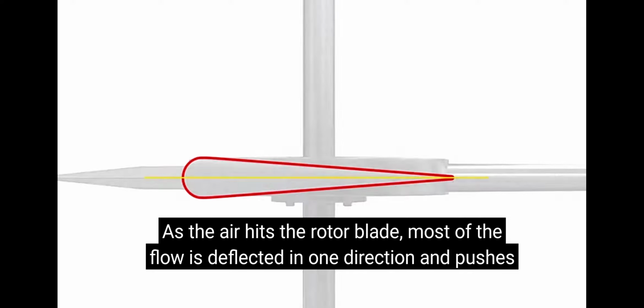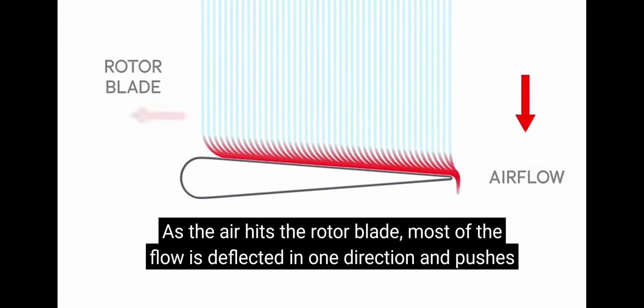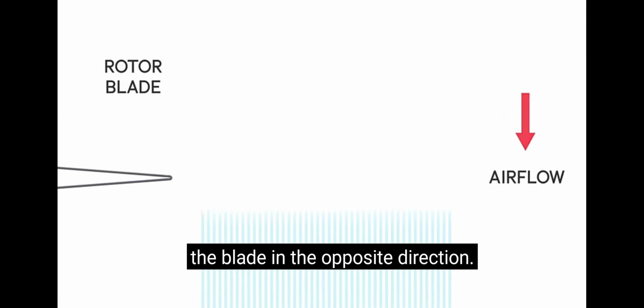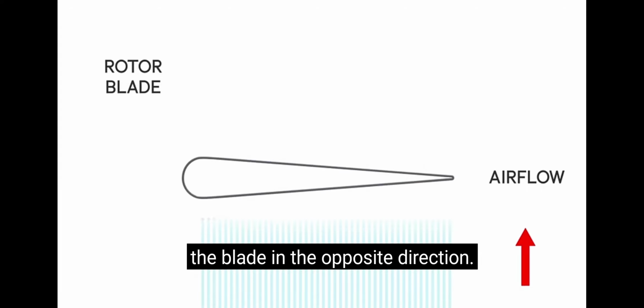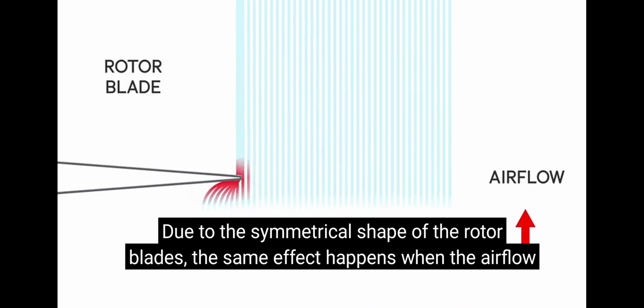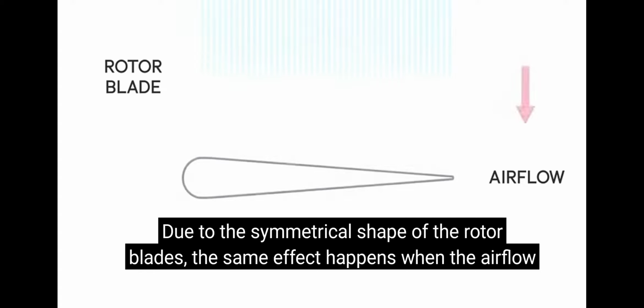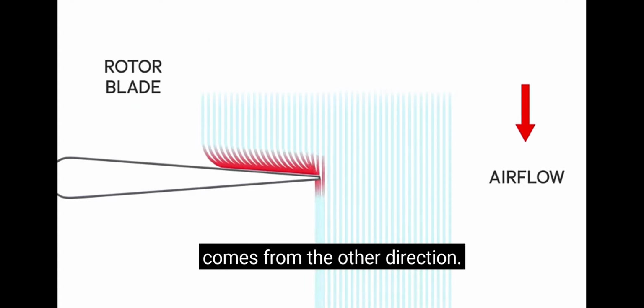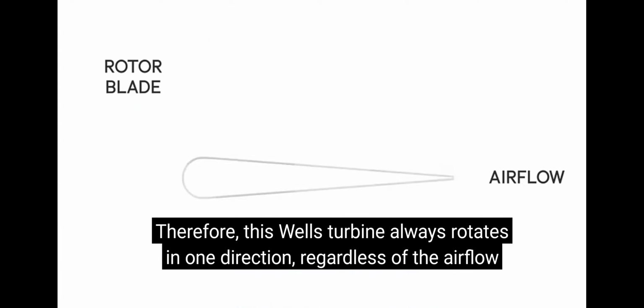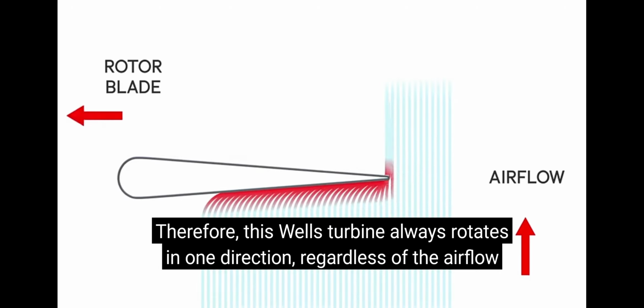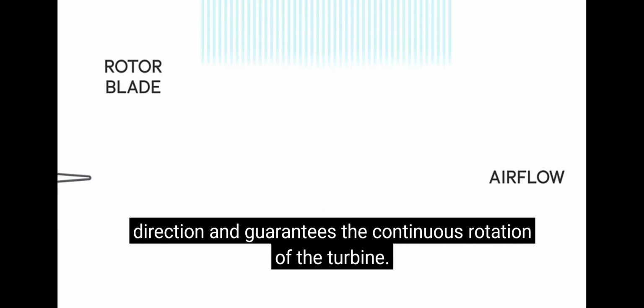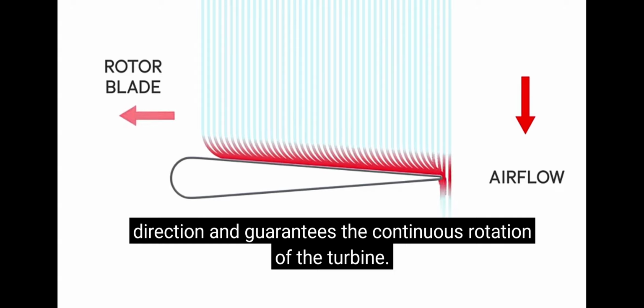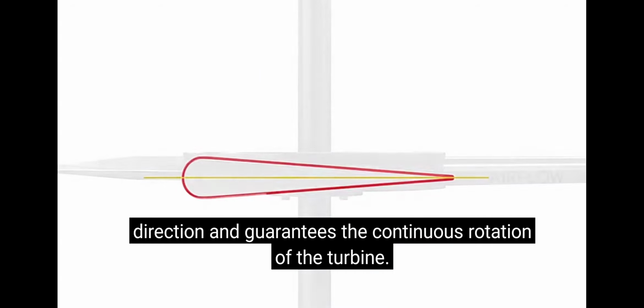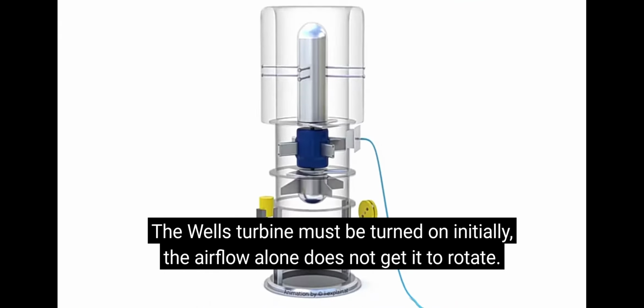As the air hits the rotor blade, most of the flow is deflected in one direction and pushes the blade in the opposite direction. Due to the symmetrical shape of the rotor blades, the same effect happens when the airflow comes from the other direction. Therefore, this Wells turbine always rotates in one direction, regardless of the airflow direction, and guarantees the continuous rotation of the turbine. The Wells turbine must be turned on initially; the airflow alone does not get it to rotate.